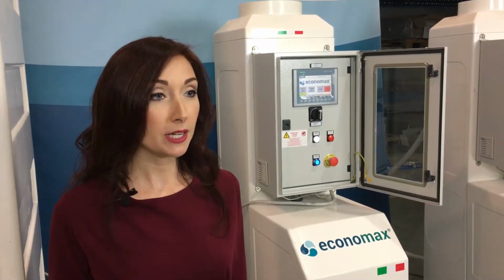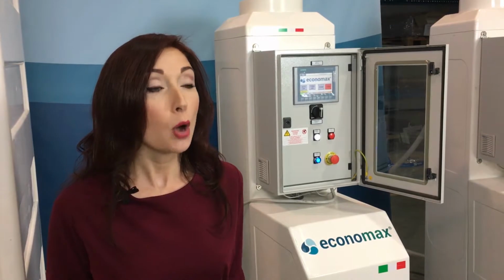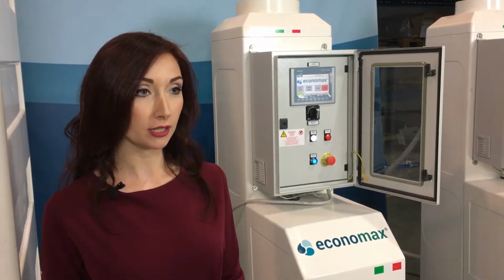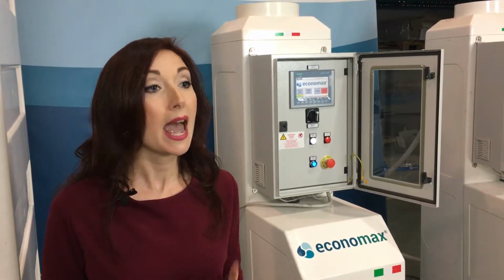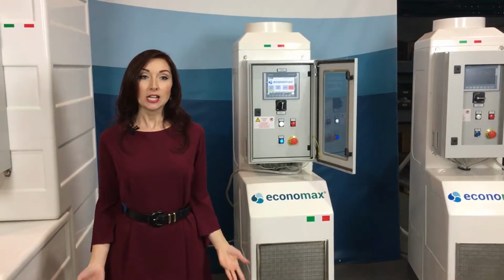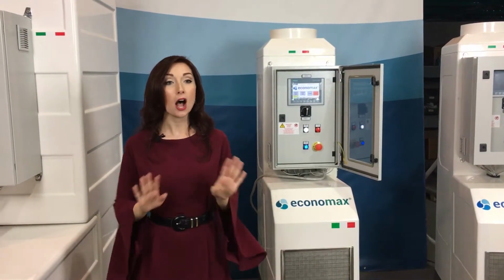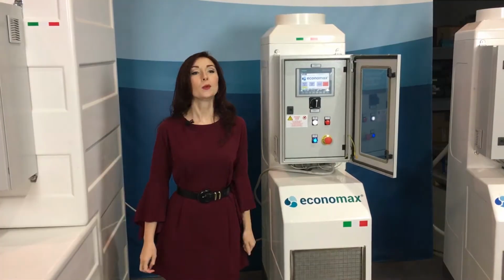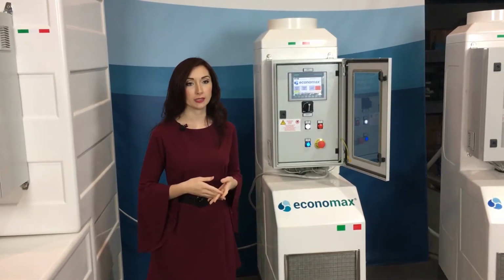We demonstrate our experience by offering an industrial PLC programmed with preset functioning parameters that regulate its functions dynamically and allow optimization of efficiency and consumption in real time. When needed, you can easily monitor and regulate all parameters directly from the touchscreen. Within the tower, you can find the main components, which are the circulation pump, managed by the inverter that pushes the water from the tower through the hydraulic system up to the machines that need cooling. The characteristics of our pump make it perfect to serve any type of workroom, even the most complex ones.